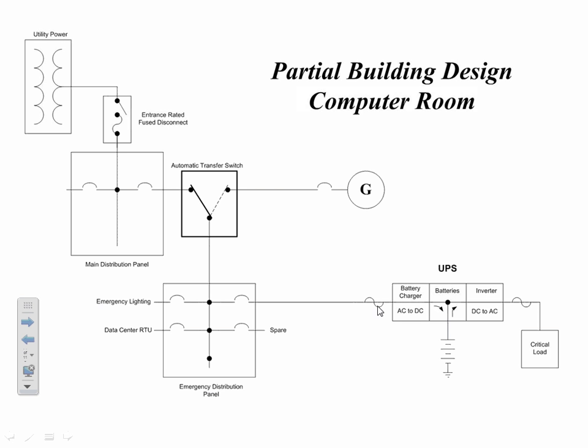Utility power comes back, the reverse is true. Voltage sensors again here, we'll see it. They'll start going through time delays, and we'll go through a time delay on retransfer. Again, we're going to make sure that the utility is really back. It's a hot day, and we want to wait for maybe 15 minutes to make sure that, yes, it's really, really back and it's powering all the loads out there. That happens, it transfers back. Generator cools down on the fourth time delay that it sees, and then finally shuts down, and we're back the way we were before.